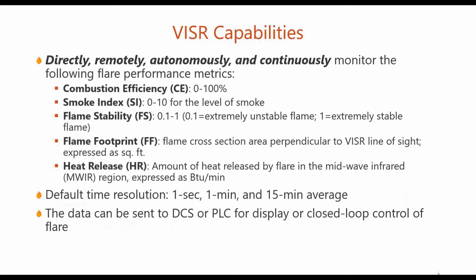And finally, heat release, which is the amount of heat released by the flare in the spectrums that we're monitoring with VISR. So this will not be the total heat release from the flare, but this heat release number will be well correlated to the total heat release from the flare. But we're not actually measuring the broad spectrum heat release. We're just looking at the slices, the midwave that VISR is monitoring.